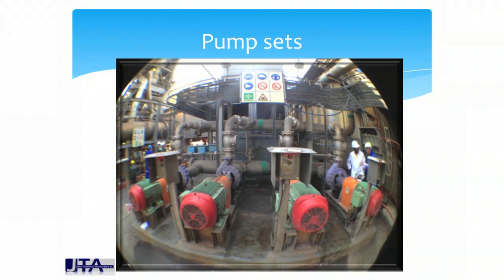So that was the one, and the pump sets of those four pumps - we found, by the way, that one pump right on the end there had recently been in for a service. It was 35% off its curve. It had just been in for a service 2-3 months before. Open impeller pumps - obviously they hadn't got the setting of the impeller relative to the casing right.